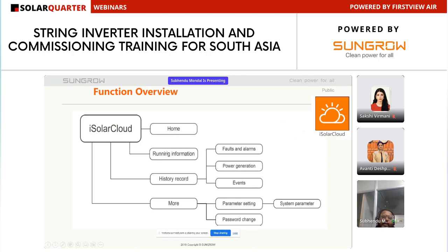So we have the iSolar Cloud app: home, running information, history record, and more options. In the home option, we can see the daily curve, date and time, and whether it is on grid or operational. Then we have running information, where we can check AC power, AC voltage, DC current and DC voltage. From history record, we can check the fault and alarm records, power generation records, and events.